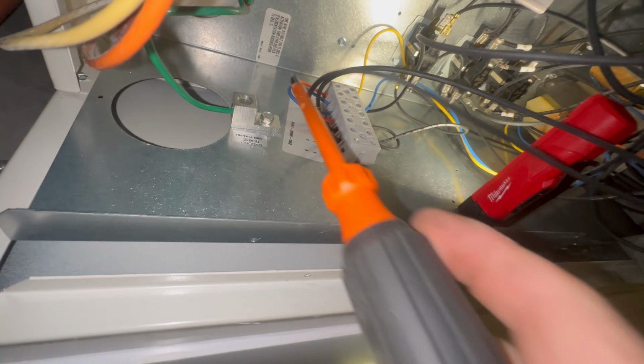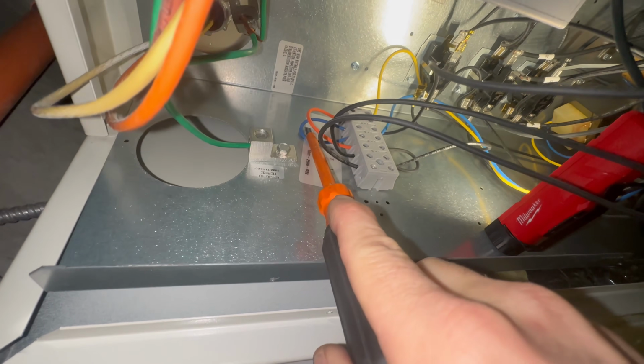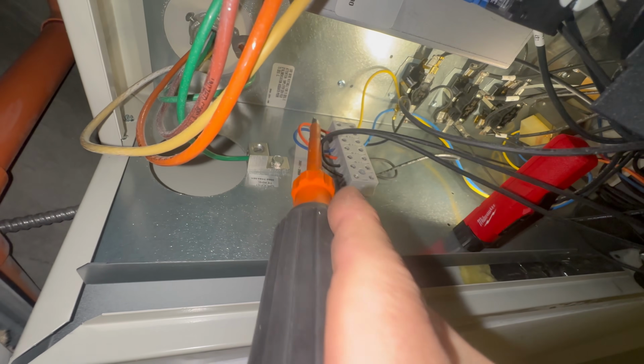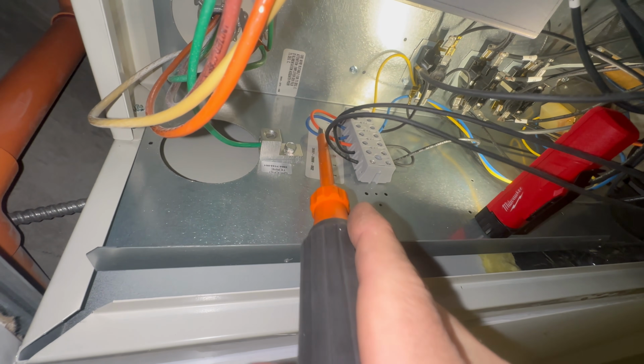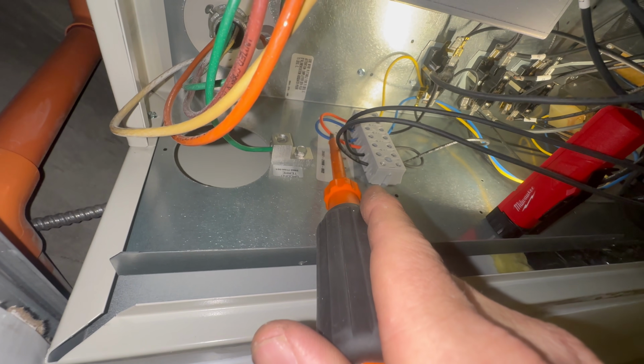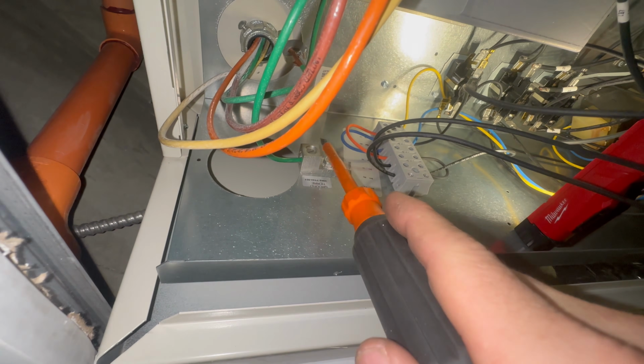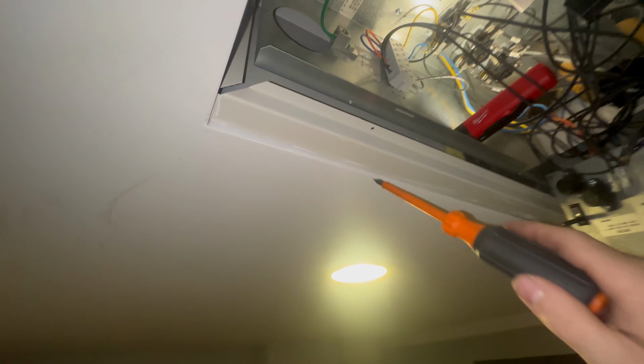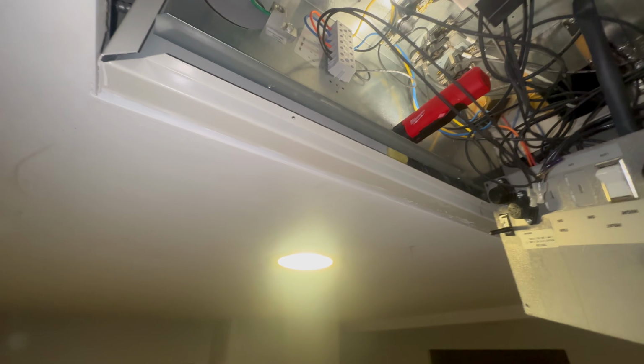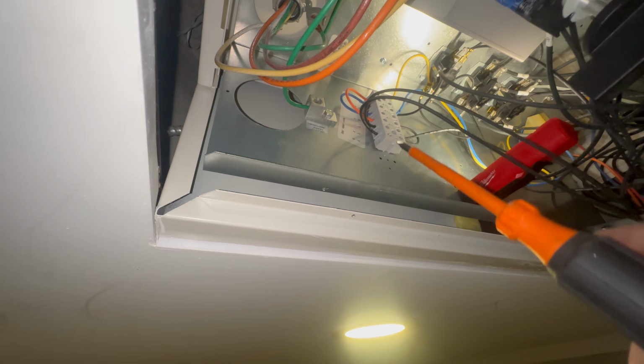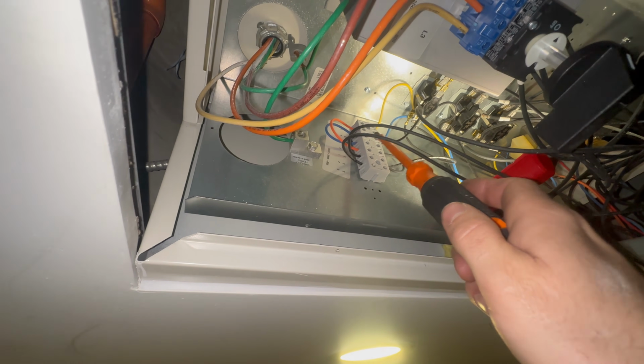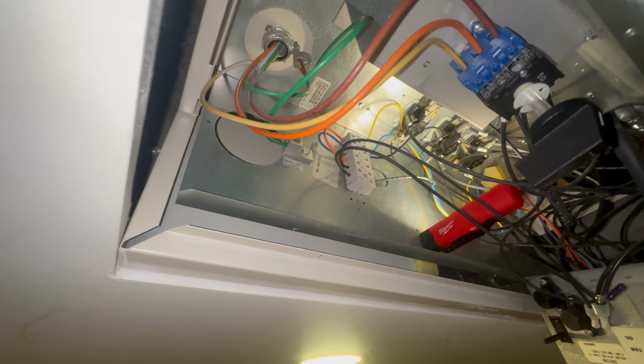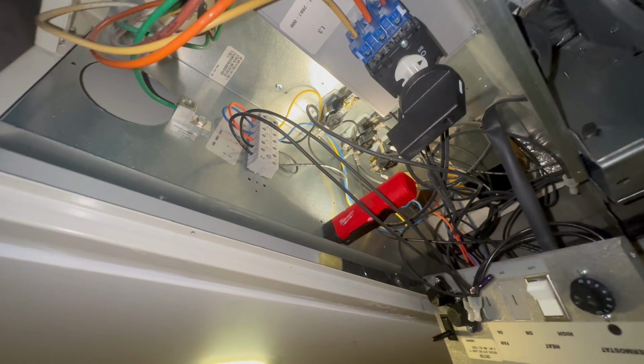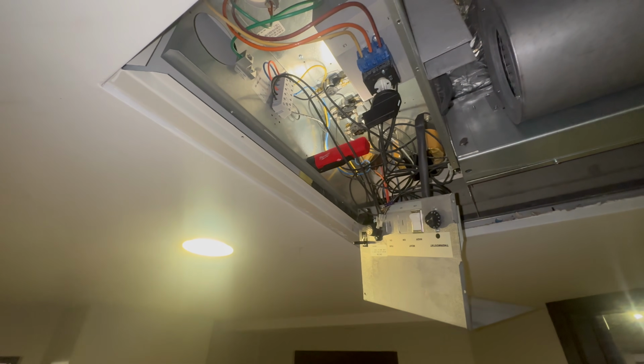And on the actual equipment itself, here's our blue jumper that I just pointed out on the diagram. I would just undo one of those terminals, put a low voltage wire into that. We could say the W wire, and I would add the W wire into this loop, mount the thermostat, I don't know, right here. And it should just operate like a normal thermostat after that. It would need batteries, unless I could run a common wire right up there and then run another wire to the red, and it would operate just like a normal household thermostat. But I'll leave that up to the supervisor here. And it really does not matter to me what they decide to do.